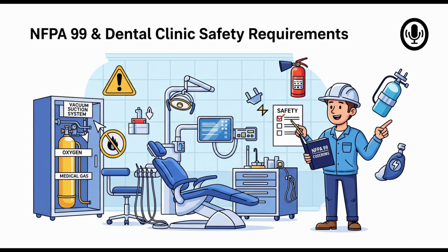What kind of tests? Just checking for leaks? Leaks are part of it, yes, initial pressure tests, but it goes way beyond that. You have to do cross-connection tests. This is critical. You verify that each gas is only coming out of its intended outlet. You pressurize one system, like oxygen, and then check every single outlet for all other systems, air, nitrous, vacuum, to ensure none of the oxygen is crossing over. Then repeat for each gas.